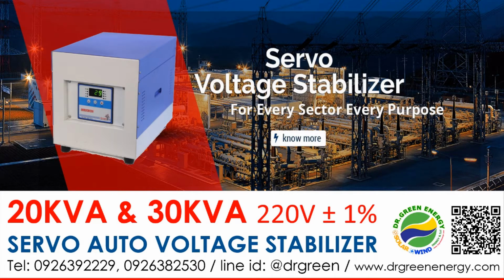The topic of today is the servo voltage stabilizer, with capacities of 20 kVA and 30 kVA. The special feature of this stabilizer is that the output is very precise, about 220 volts plus or minus 1%, which is the best in class when compared to servo automatic voltage stabilizers in the market.